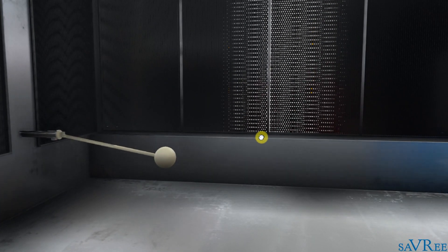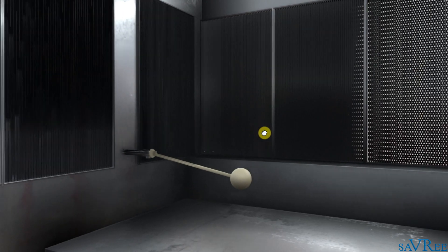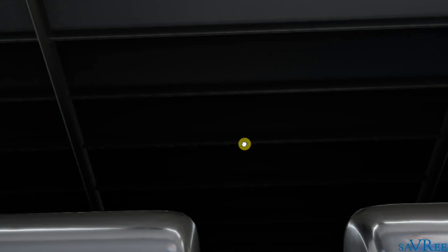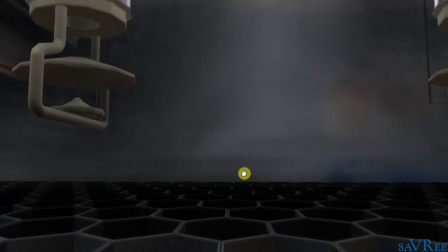The air is going to be drawn up through the fill. So let's pass through the fill as well. We can see we'll go through this hexagonal shape. Off we go. The fill is not a straight shape because we actually want to promote turbulent flow because then we get a better evaporation effect and cooling effect between the water and the air. So now we're back above the fill.